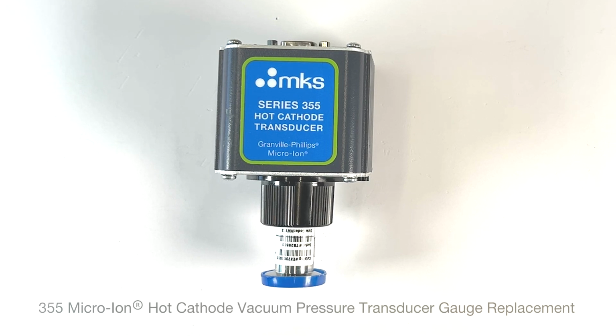This video is to demonstrate how to replace the gauge portion of an MKS Series 355 hot cathode module or transducer. This is a simple process that can return a failed unit back to working order quickly and easily. The sensor in the gauge contains a sensing wire or filament. When broken, the wire cannot be repaired or replaced, so the whole sensor unit with a new filament will need to be installed to repair the unit.